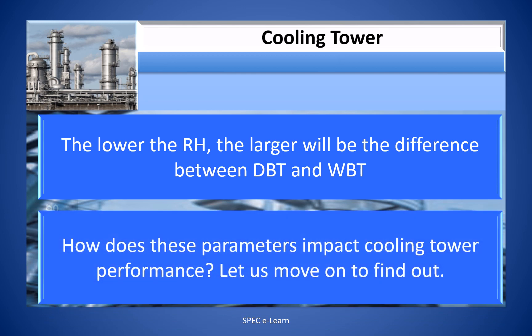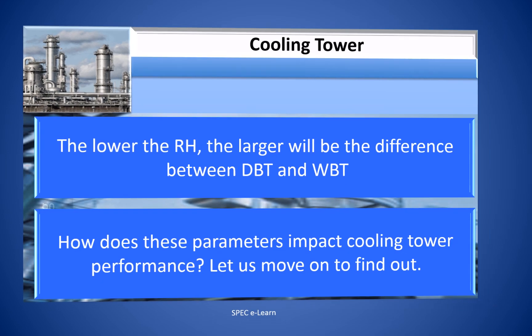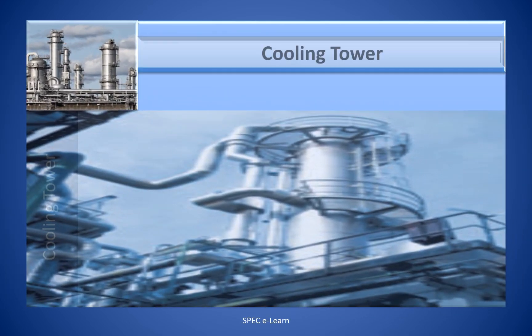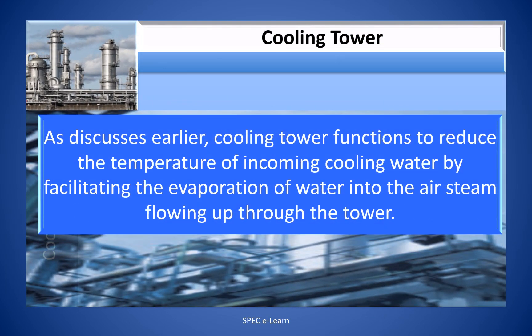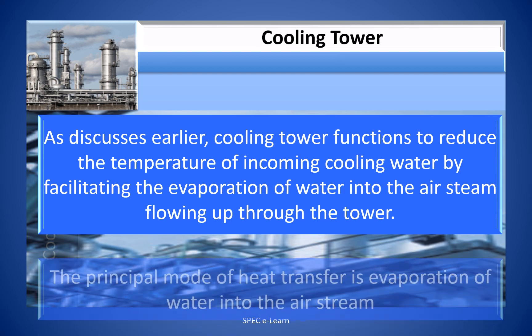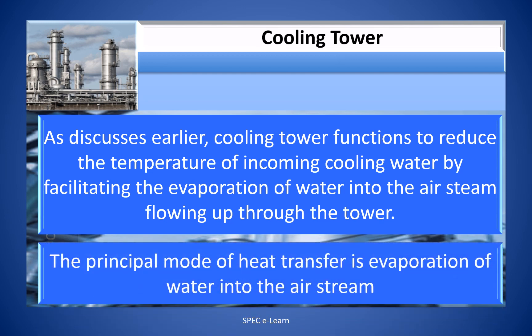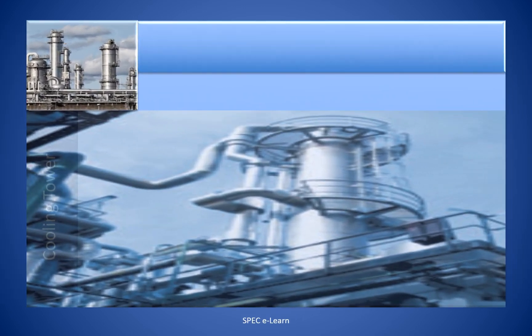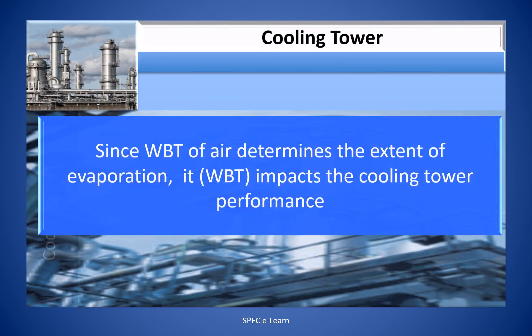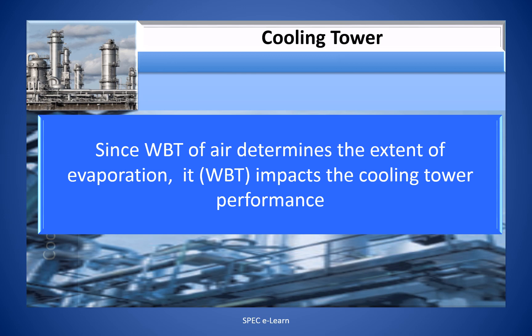How do these parameters impact cooling tower performance? Cooling tower functions to reduce the temperature of incoming cooling water by facilitating the evaporation of water into the air stream flowing up through the tower. The principal mode of heat transfer is the evaporation of water into the air stream. Since the WBT of air determines the extent of evaporation, it directly impacts cooling tower performance. When WBT is lower, the water exiting the cooling tower will be at a lower temperature.